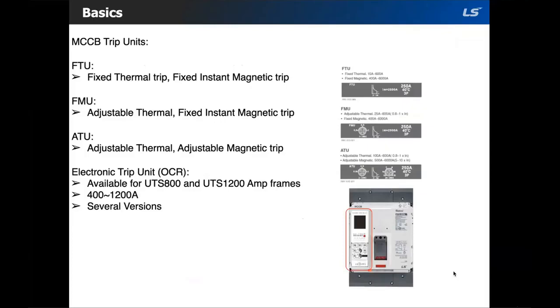Now that we understand the different offerings within the MCCB family, let's cover the various trip unit options. For the UTE 100, UTS 150, 250, 400, and 600 amp frame sizes, there are three types of trip units. These are FTU, which contains both fixed thermal and fixed magnetic. And there is FMU, which would be adjustable thermal, but a fixed magnetic element. Finally, ATU, which is both adjustable thermal and magnetic.